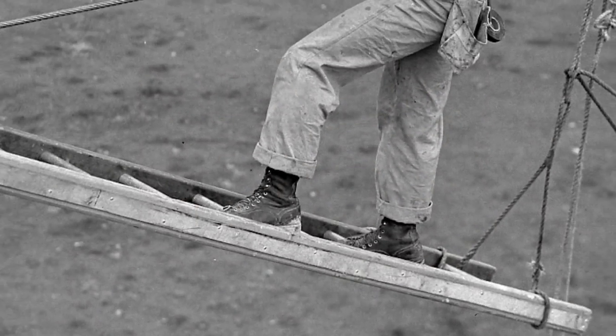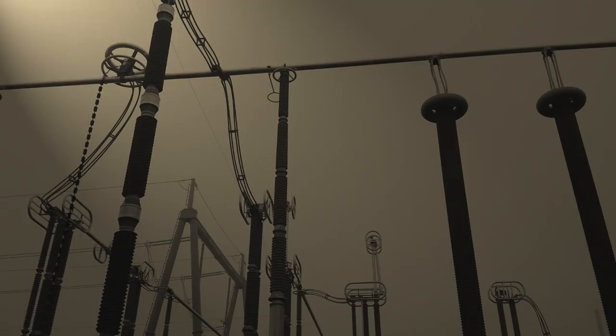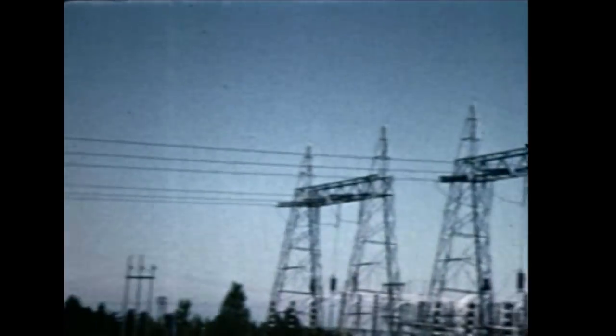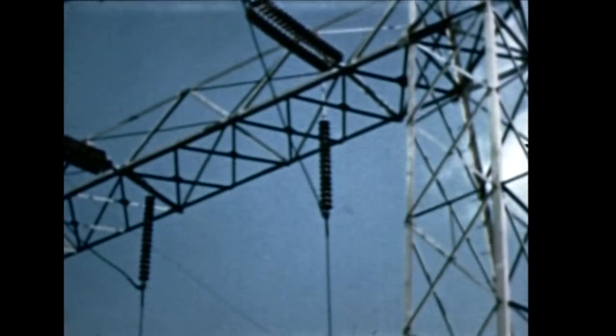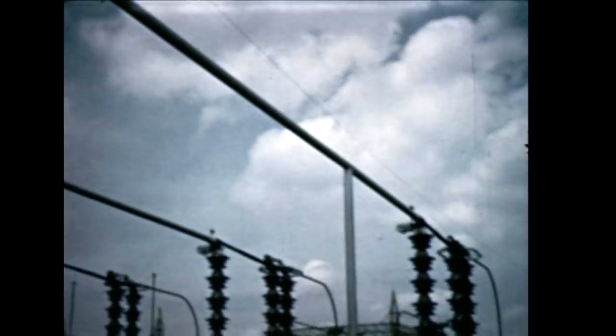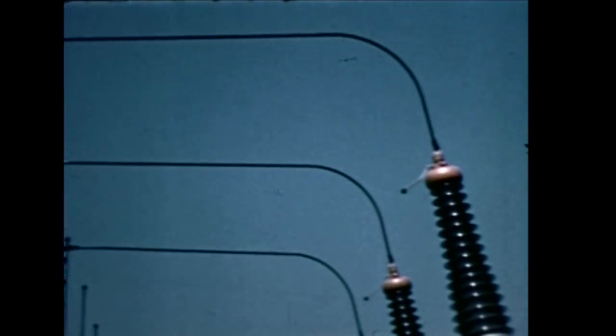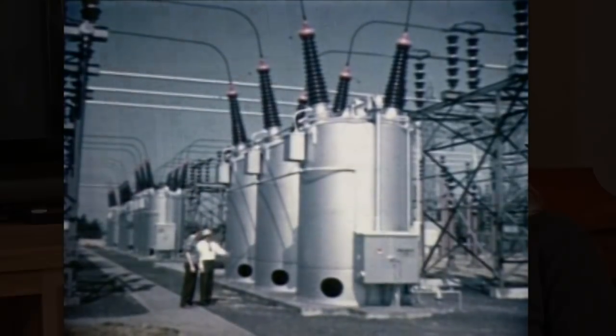There are time frames that you need to pay attention to in power system operation. The shortest time period is right after an event happens, like when a breaker opens, it produces a switching transient, and you want to make sure that your system is such that the voltage spike doesn't put the equipment beyond their rated capabilities.